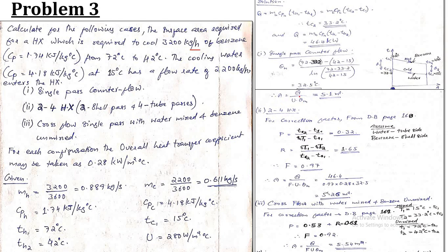For the single-pass counter flow heat exchanger, use q = U·θ_m·A. With q = 46.4 kW, U = 280 W/m²°C, and θ_m = 32.5°C, the surface area A = 5.1 m².